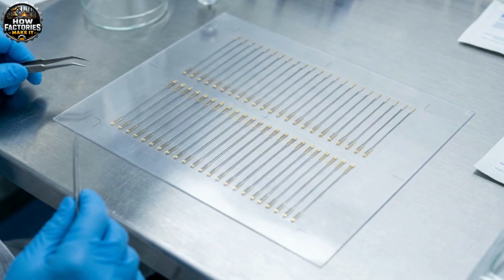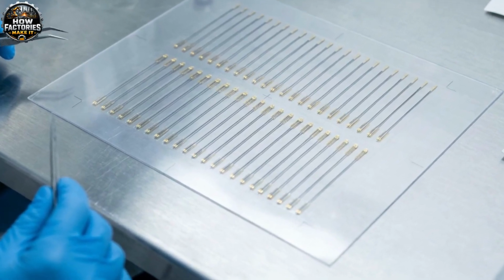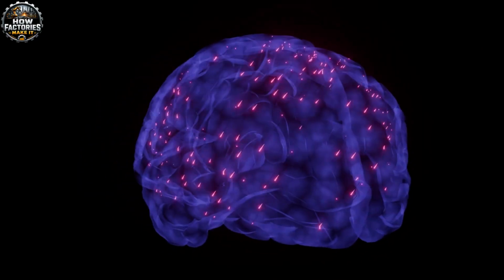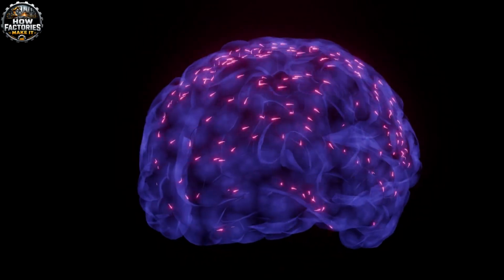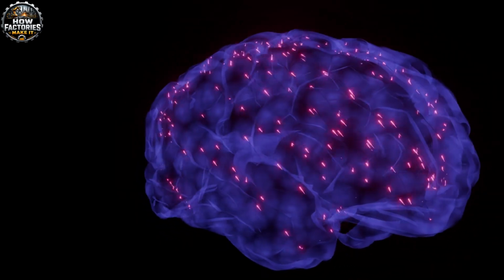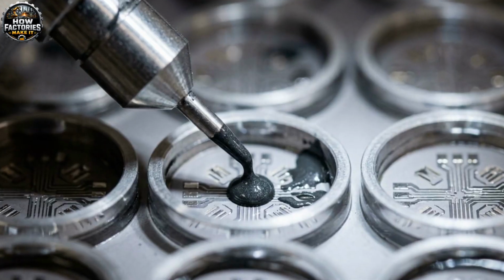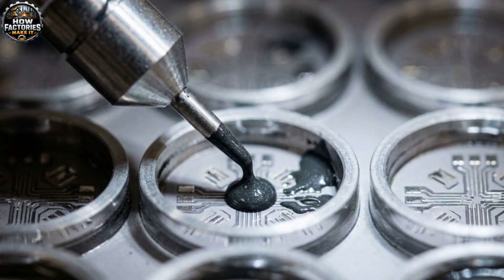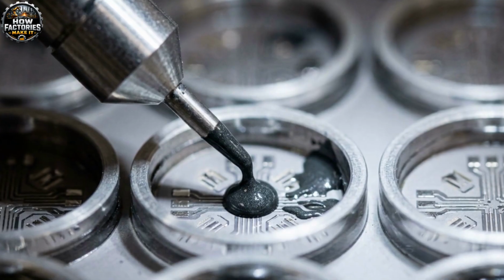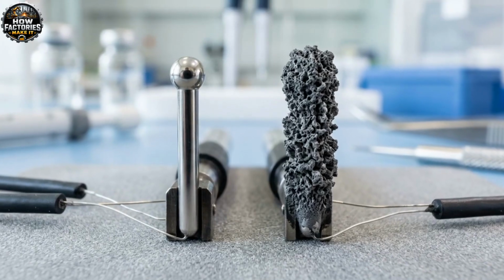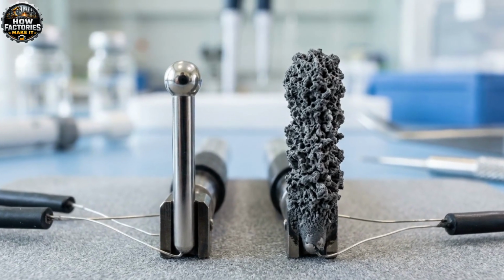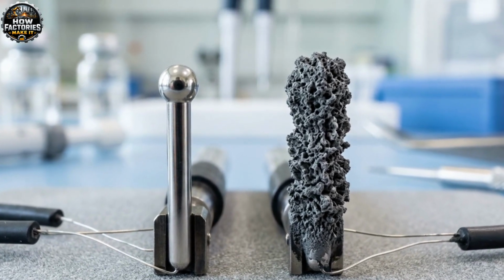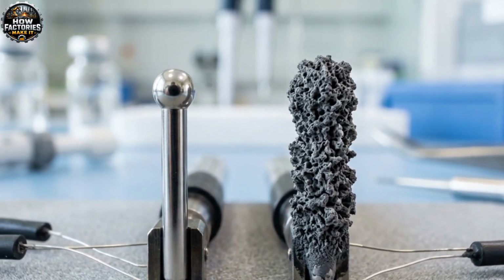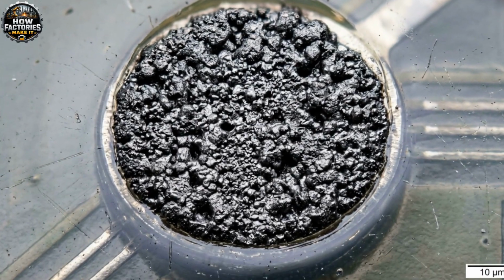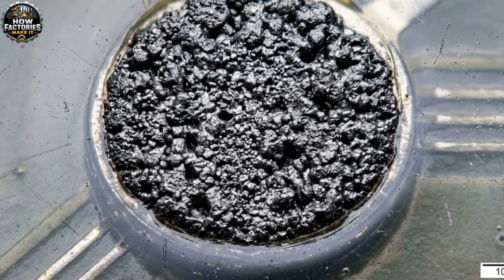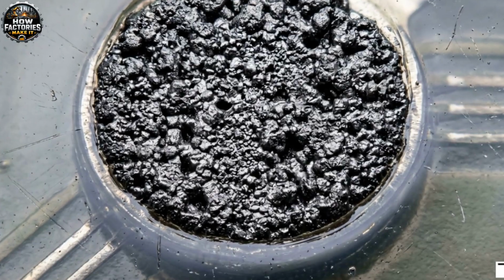The exposed electrode contacts are extremely small. A small surface area can create high electrical impedance, making it more difficult to collect clean neural signals. To improve performance, the electrode contacts may receive a specialized conductive surface treatment. Published Neuralink prototypes tested materials including iridium oxide and the conductive polymer PEDOT. These coatings increase the electrode's effective surface area without dramatically increasing its physical dimensions.